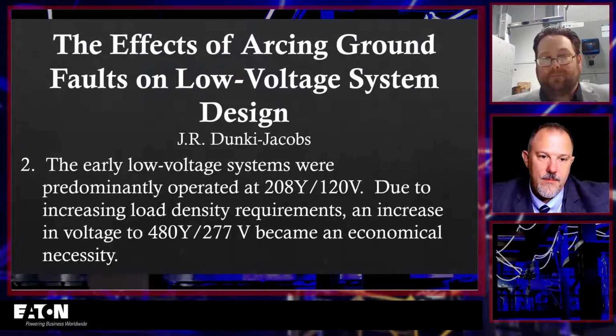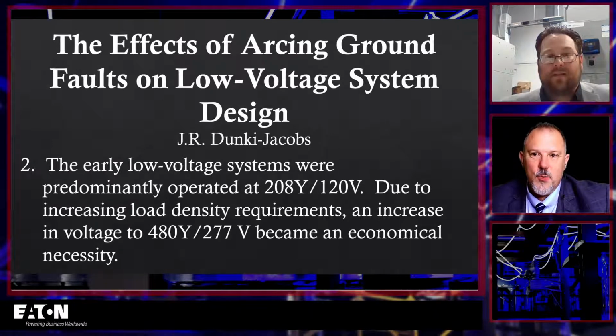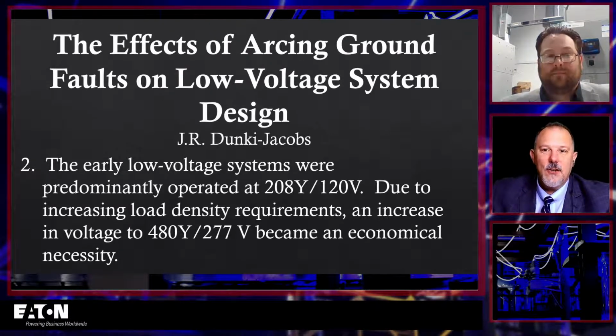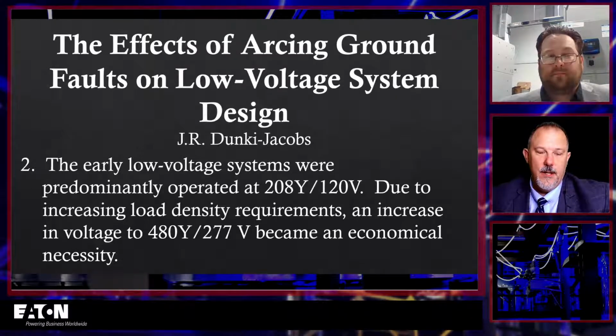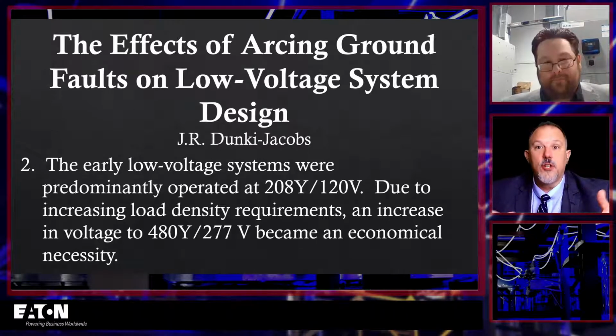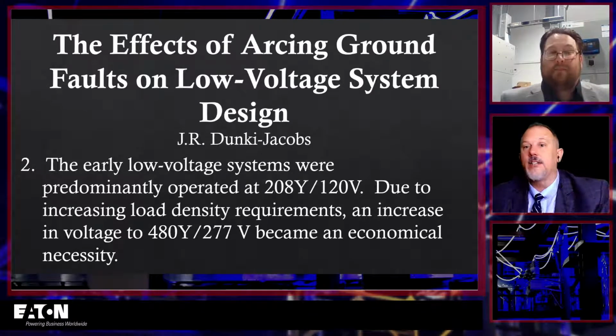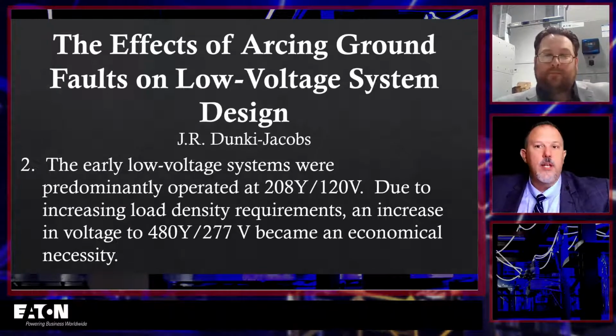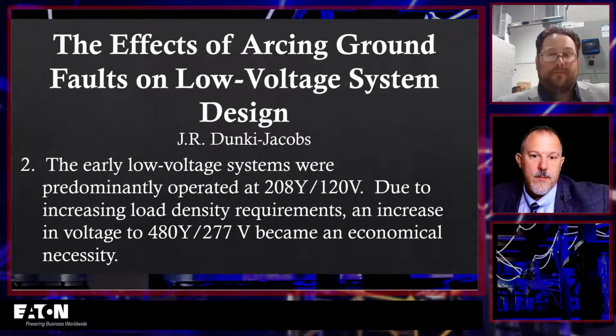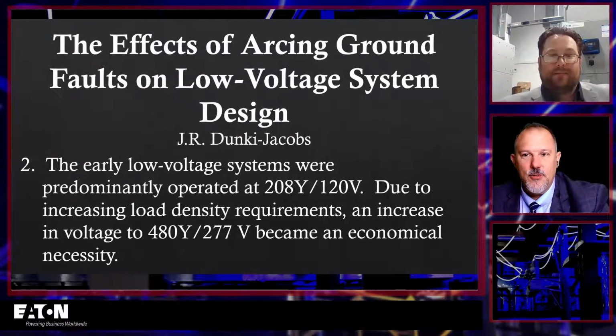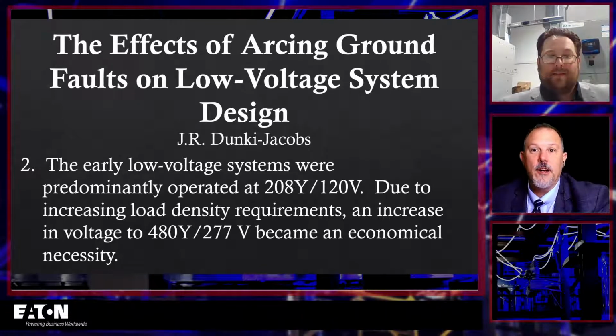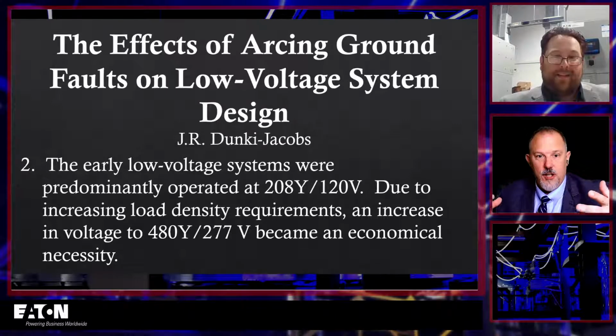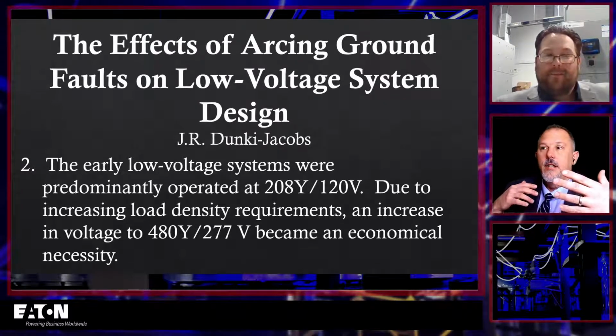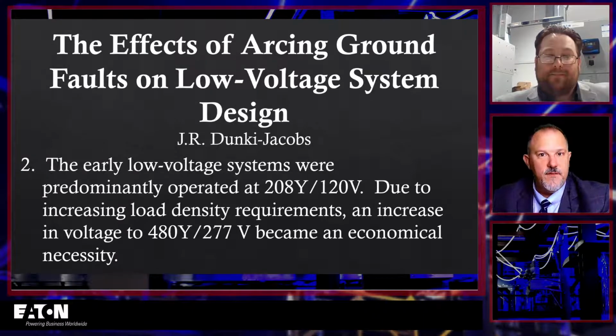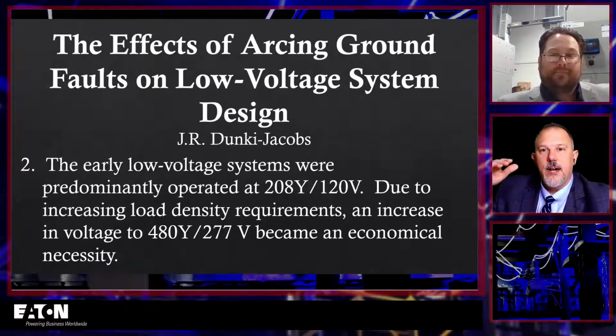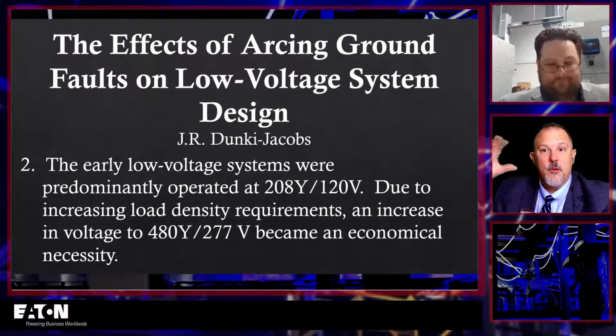Okay? Now, the other change. Most systems were 208 volts. And then they started to add more loads. They had more load density requirements, and they needed more voltage to transport it, because why do we go to higher voltages, right? We use smaller conductors and have lower losses. I can transport power across a campus, and then I bring it down. So they went from 208 to 480. And what is voltage in a system if I compared it to water? It's pressure, right? So my voltage will push that current, and that creates changes in fault currents, all that good stuff. When my voltage goes up, my currents will come down though, right? Because I have more pressure behind it. So my currents come down.